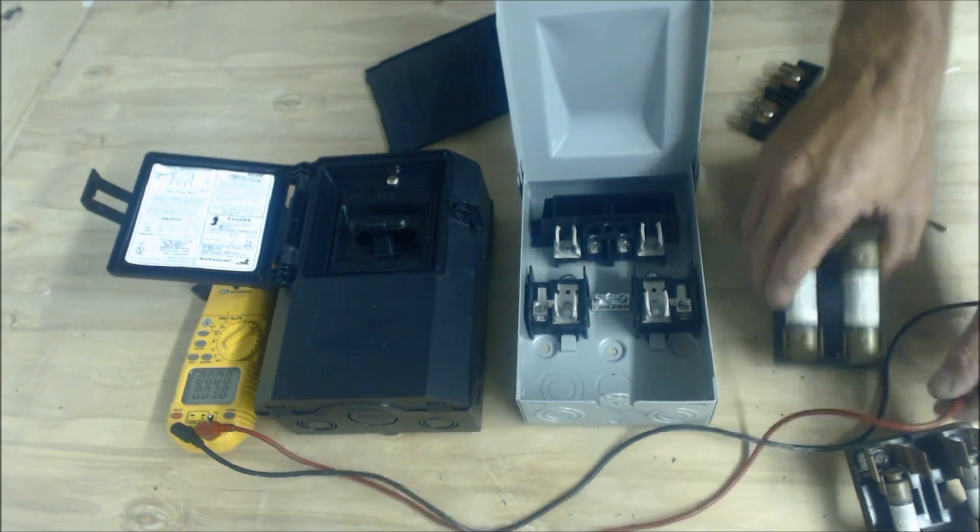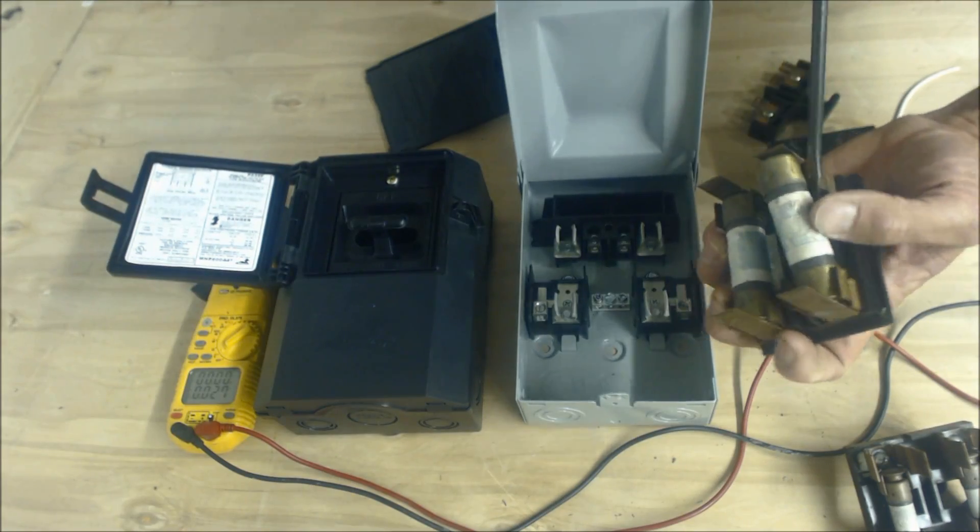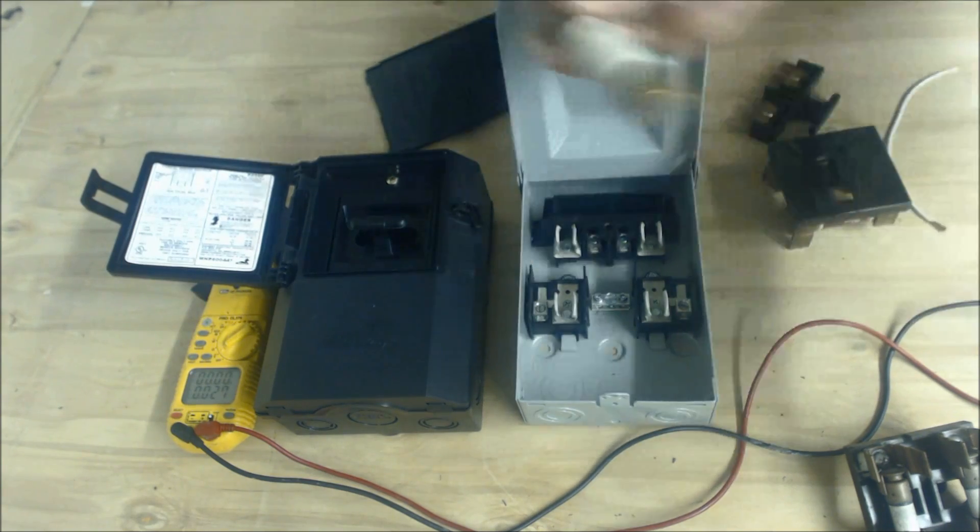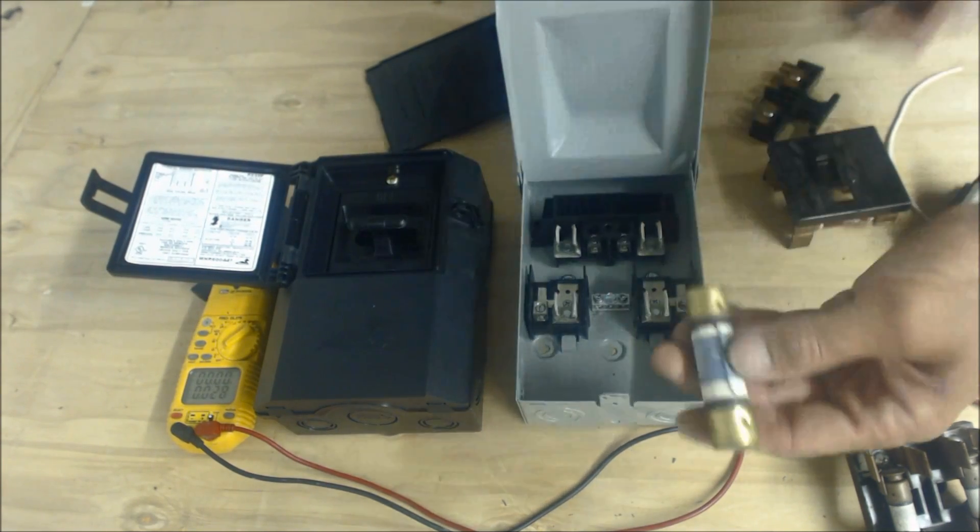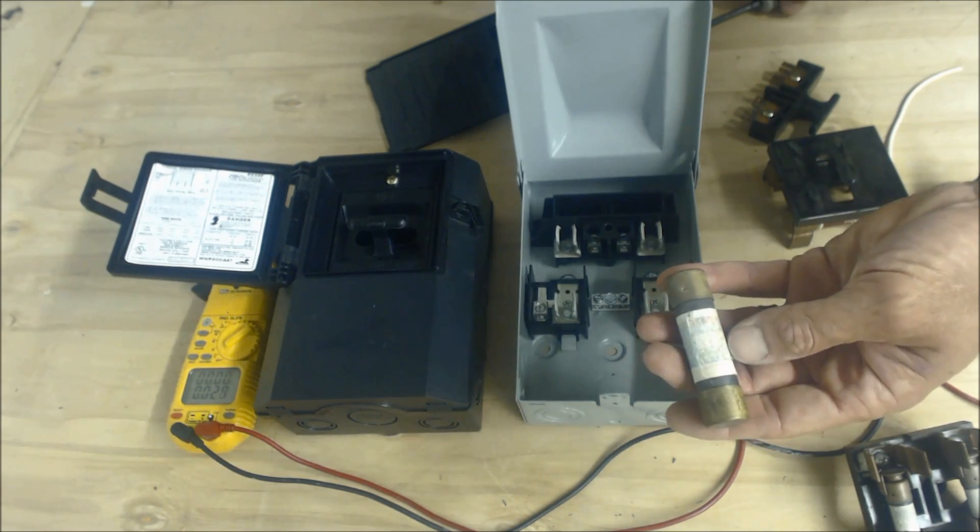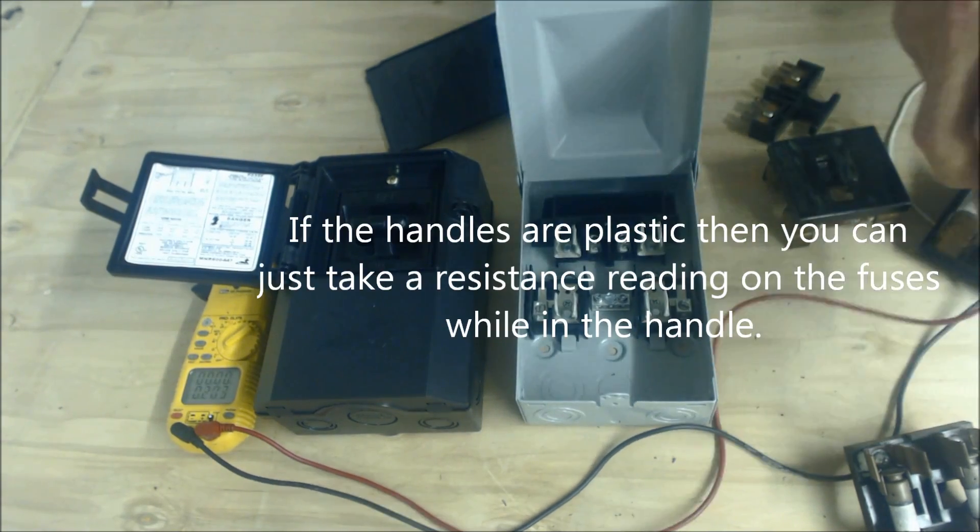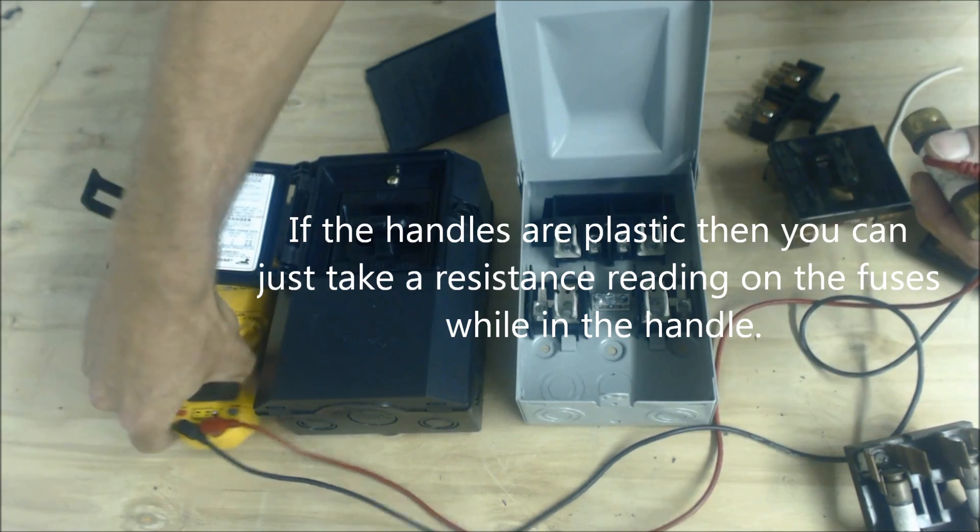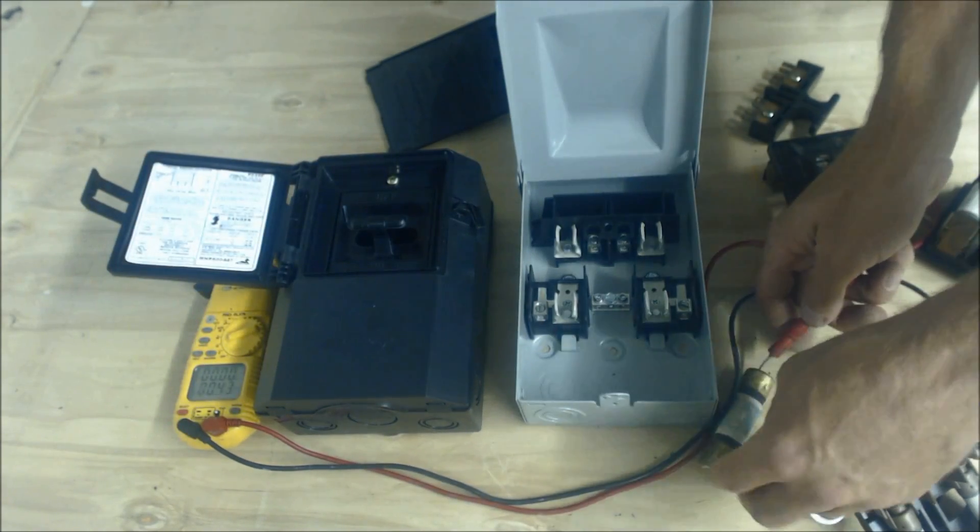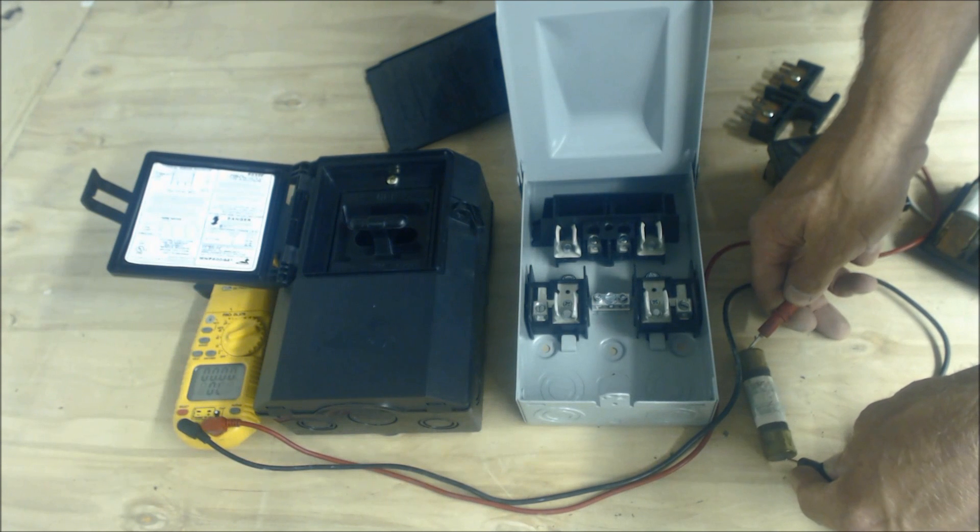And as far as fuses go, you can just pop them right out and you can take a resistance reading on them. So you can just take your multimeter, turn it to resistance, and check it. It should not really have any resistance on it.